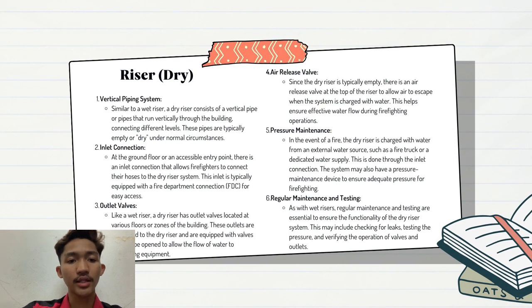There are 6 items or components in a dry riser. The first one is the vertical piping system. Similar to a wet riser, a dry riser consists of a vertical pipe or pipes that run vertically through the building, connecting different levels. These pipes are typically empty or dry under normal circumstances. The second one is the inlet connection. At the ground floor or an accessible entry point, there is an inlet connection that allows firefighters to connect their hoses to the dry riser system.